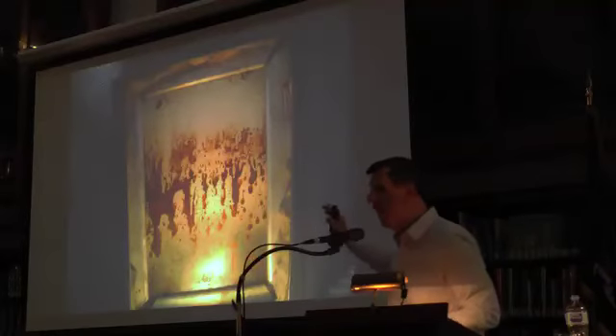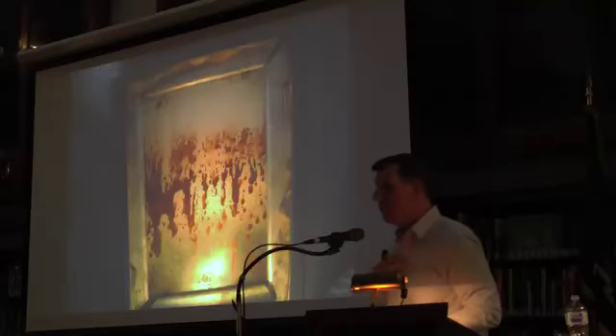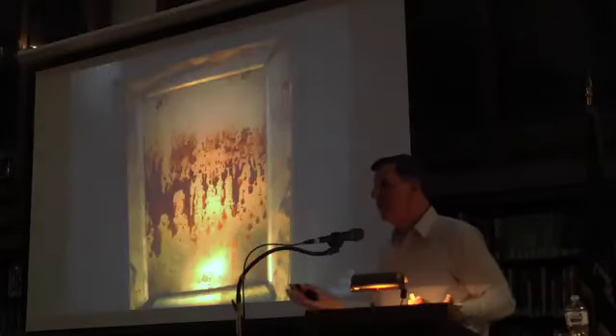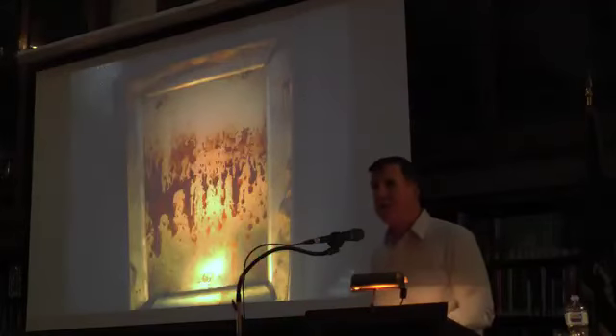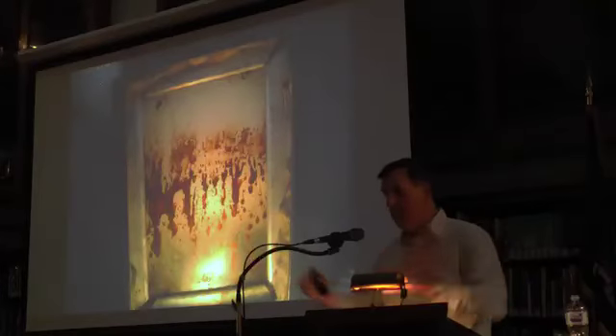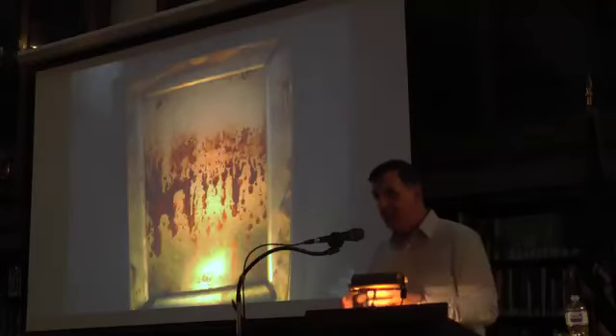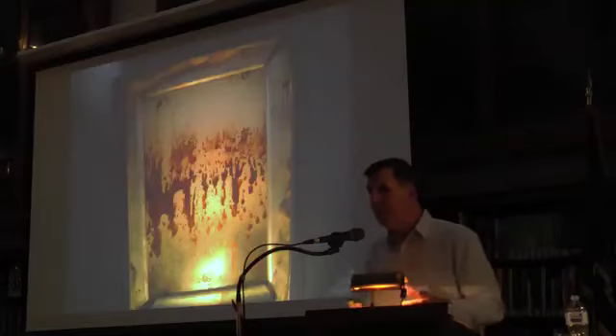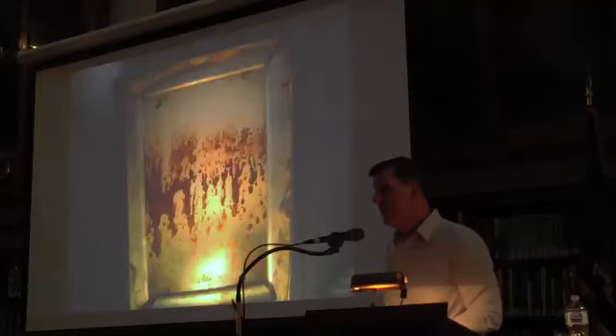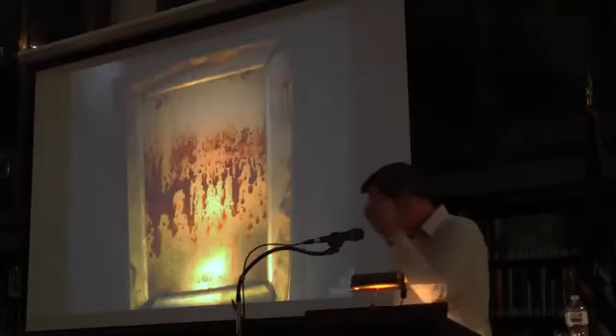This is the nature of modern boilers that by federal law have to meet a certain standard in efficiency. Steam boilers used to be 60% efficient. Everybody thought that was great. But now if you got to be up in the 80s, the only way to do that is to reduce the metal. So you're firing the same amount of flame into something that's way smaller, and that's what causes that violence. So you got to follow the instructions. That's my advice to you.